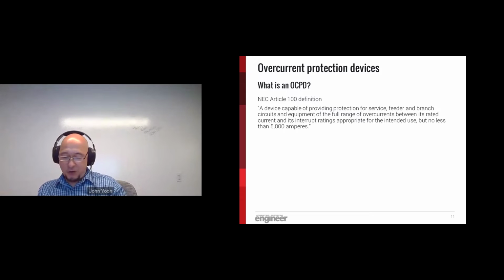So, that brings us to the question. We have two different types of conditions, overloads and faults. How do you safely interrupt this abnormal flow of electricity? With an overcurrent protection device. Well, let's continue with another excerpt from the Article 100 definitions, the definition for an overcurrent protection device that's on this slide. So what qualifies as an overcurrent protection device? This could be a fuse, it could be a molded case circuit breaker, it could be a protective relay, whatever. However, what isn't noted here very conspicuously is a timing requirement, how quickly that device needs to operate. While the code in some cases makes mention of how quickly a device needs to operate under very specific conditions, it generally is more a function of the UL standard associated with that particular device type.